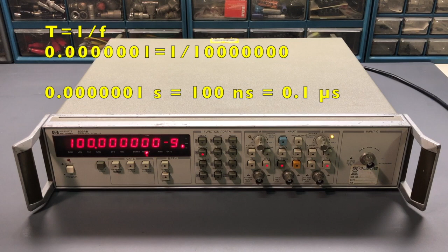All right. Now, this has 3 input channels. So we have channel A here, we have channel B, and then we have channel C input. Channel C input is 50 ohms. These can be high impedance or 50 ohms selectable. I have them set to 50 ohms. This is always 50 ohms. And the channel C input is used for 90 to 1300 megahertz. It will actually read frequencies under 90 megahertz, but typically you use it for just the higher frequency input.